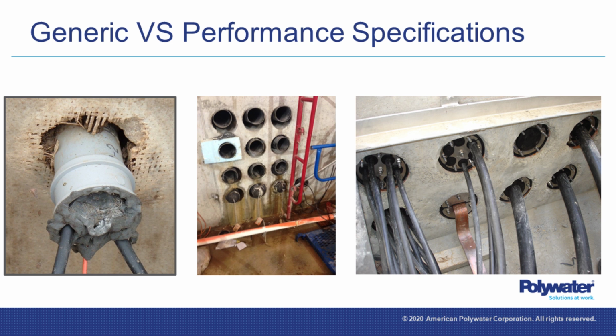Otherwise, when it comes to cable pulling, if you're using good cable pulling equipment and you've planned the pull, there's really no difference that you can't overcome by pulling one single conductor in a conduit versus multiple conductors. It happens every single day.